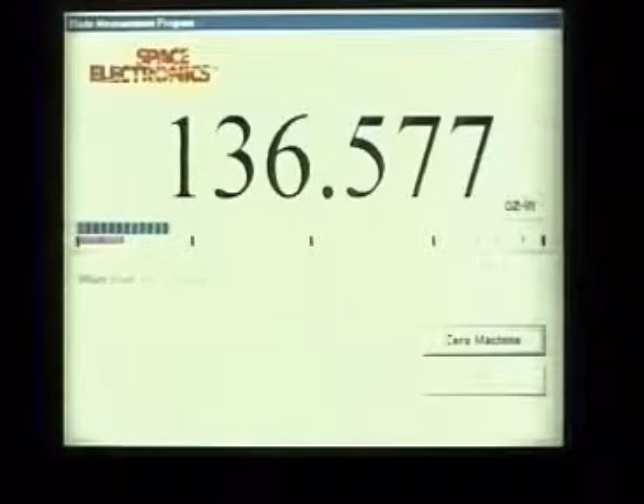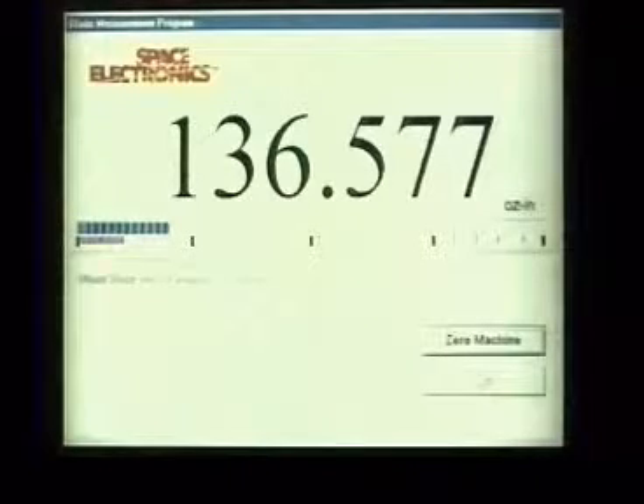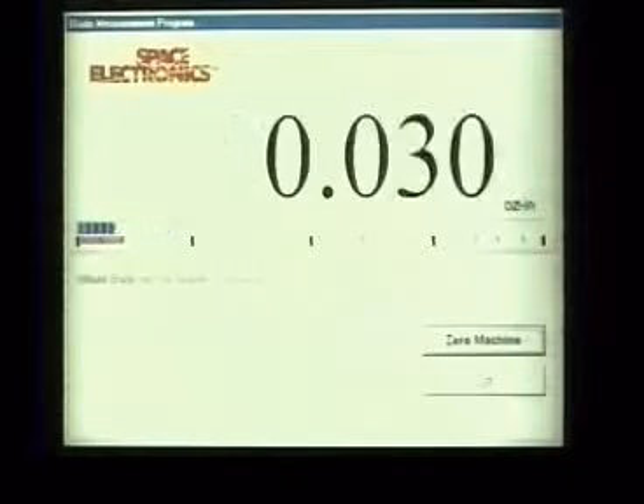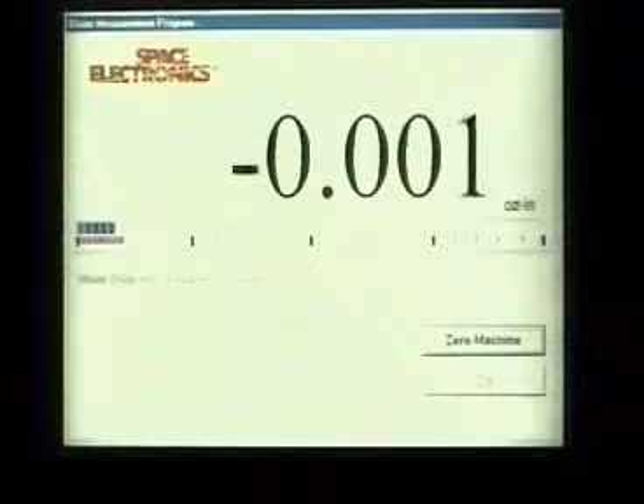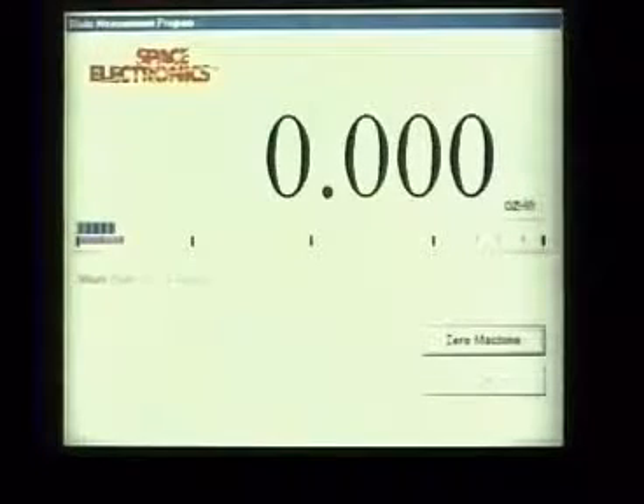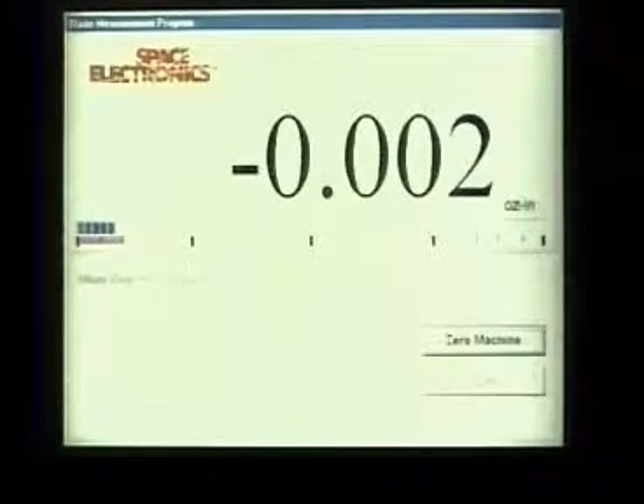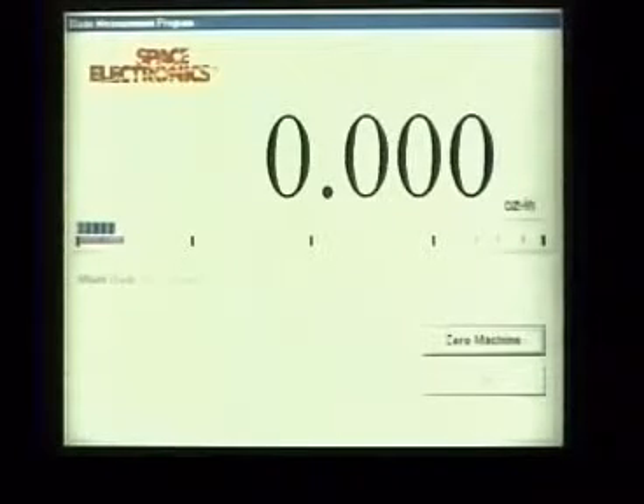Now I'll exit the setup mode and go back into measurement. And now what we're observing is a more precise moment. Instead of being 136.58, it's 136.577 ounce inches. And now we can see even more precisely what the true variation is in reading. First we observe that the zero point is actually drifted by one thousandth of an ounce inch. If I want to, I can reset that zero so that it's exactly on zero. We're now dealing with such small variations that if I bump the machine when I do that, then it gives me a slight error.